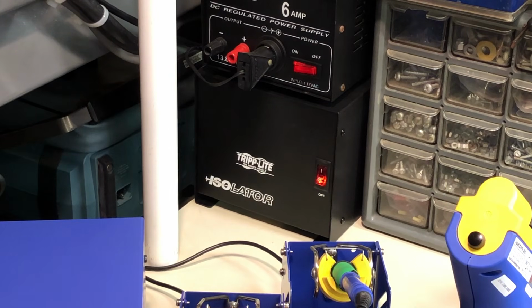Here we are over on the corner of the workbench looking at the isolation transformer that I use on my isolated dim bulb tester. So you can see it's made by Tripp Lite, and it says isolator. It has a nice illuminated rocker switch for the main power on and off. It has a steel enclosure. It's based on a toroidal type transformer design. And on the back panel, it has the AC outlets that are connected to the secondary of that toroidal transformer. So the reason that I wanted to mention this isolation transformer is because if you pick up one of these Tripp Lite isolators, they are not in fact an isolation transformer as produced by the manufacturer, and here's why.